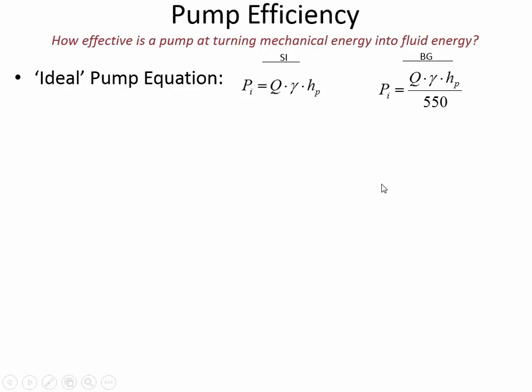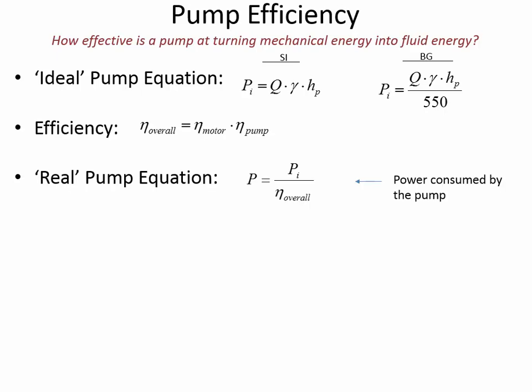Okay? Now in the case of BG units, the flow rate would be cubic feet per second. The unit weight is pounds per cubic foot. The pump head is in units of length, so it's feet. And then this 550 converts those three terms into horsepower. So this is ideally. This is how much power is required if the pump and the motor were 100% efficient. But they never will be.